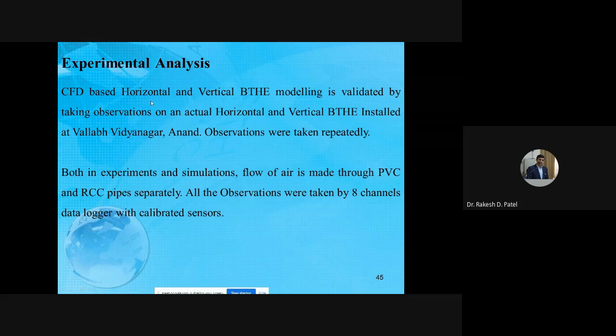The CFD based horizontal and vertical heat exchanger modeling is validated by taking observations on an actual horizontal as well as a vertical heat exchanger installed at my place. Observations were taken repeatedly, both in the experiment as well as in the simulation. Flow of air is made through PVC as well as RCC pipe separately. All the observations were taken by an 8-channel data logger with a calibrated sensor.